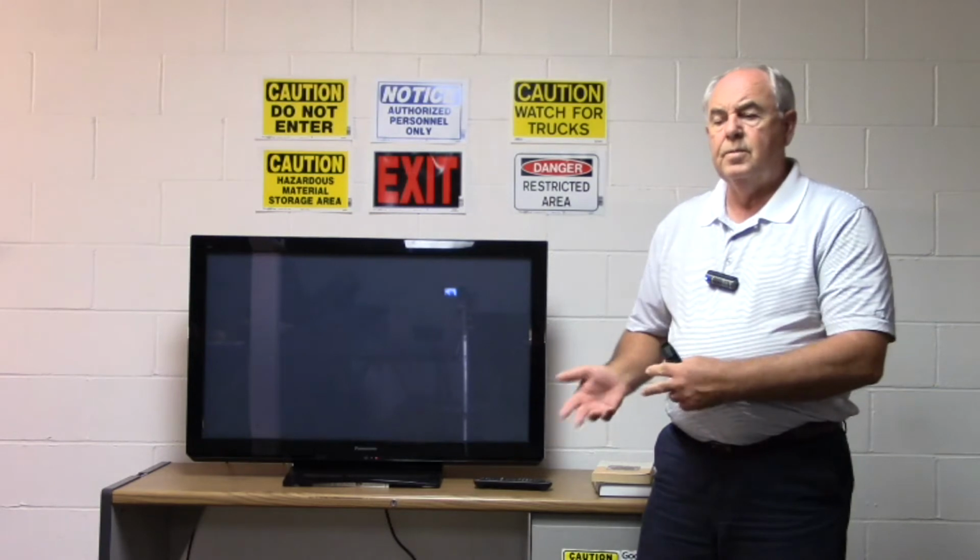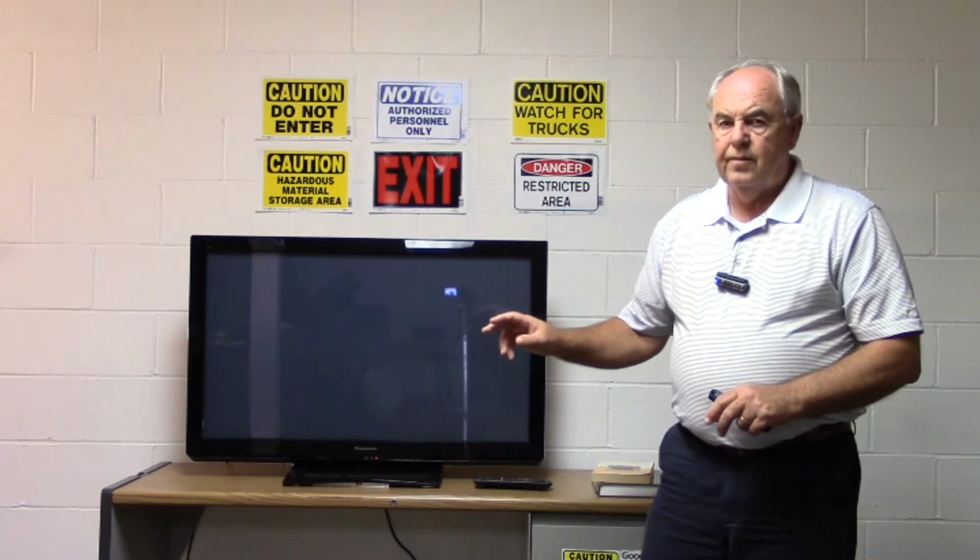Again, it's the OSHA regulation. It comes under 29 CFR 1910.157. Spend some time reading that. Spend some time examining your fire extinguishers. Keep in mind, fire extinguishers have to have an annual inspection on them, which normally is the company that provides them. They'll take care of that inspection for you. But the company itself, someone in your facility, should be checking those fire extinguishers at least once a month.